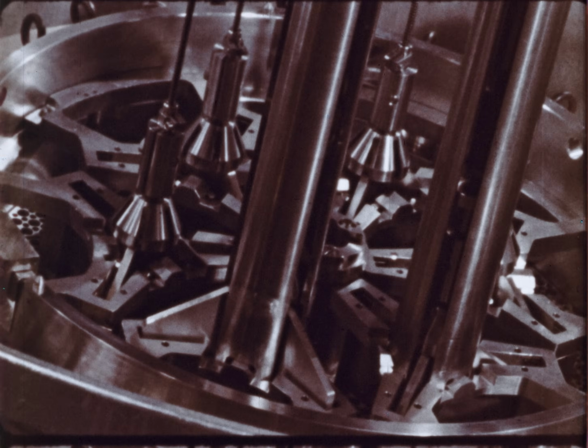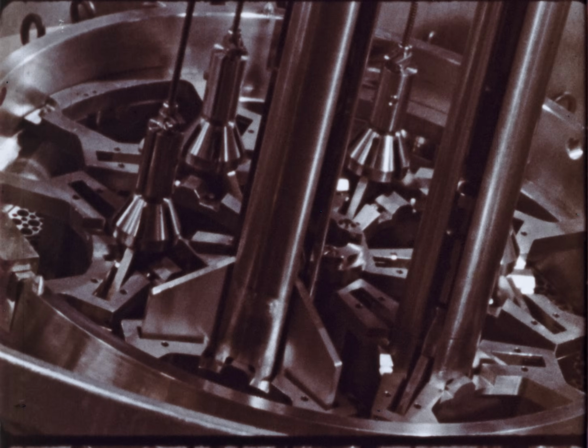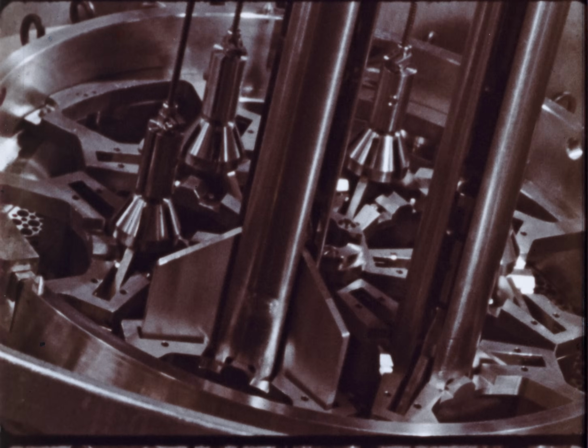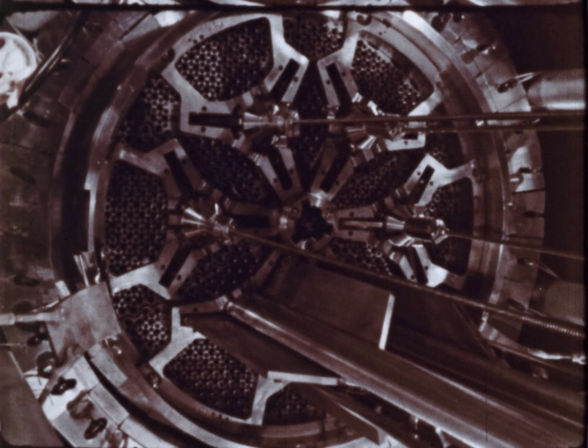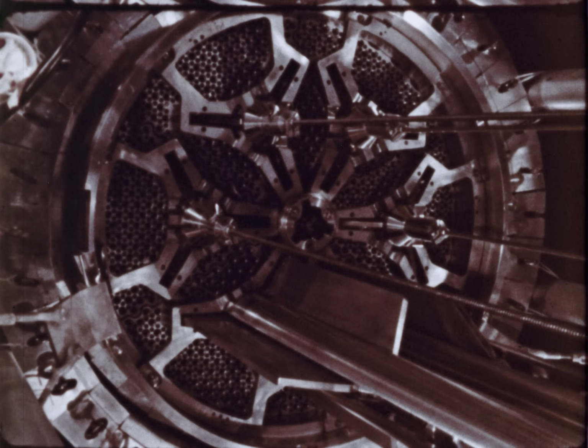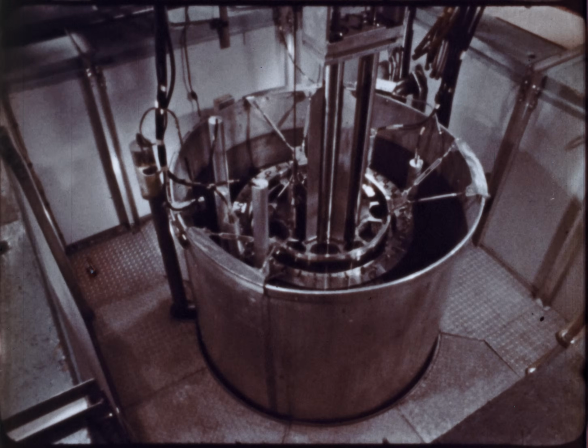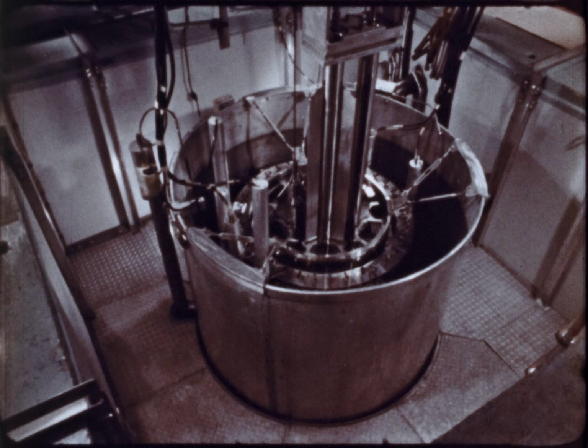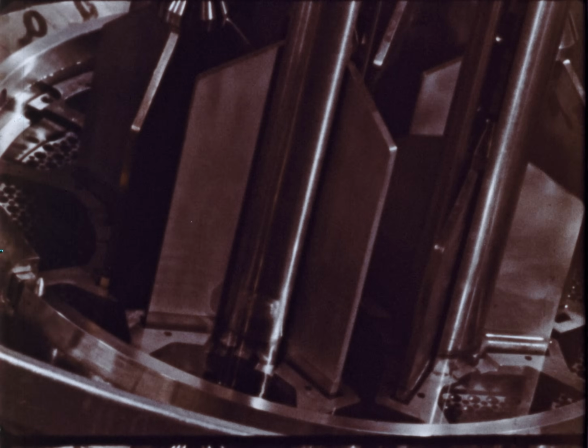Y-shaped control rods start, stop, and control the rate of reactivity. The Y rods contain europium oxide, stabilized with titanium oxide, and mixed with stainless steel powder to form a cermet. There are 6 of these rods in the core. When all of the 6 rods are fully inserted, the reactor is subcritical. Fission cannot take place. As a safety margin, the core is subcritical with only 5 rods fully inserted, or even with 4 rods inserted and 2 in the operating position.